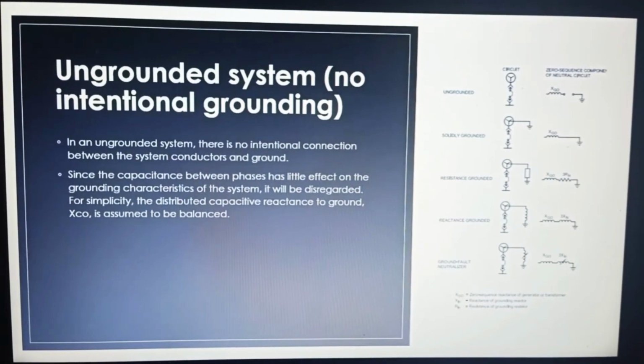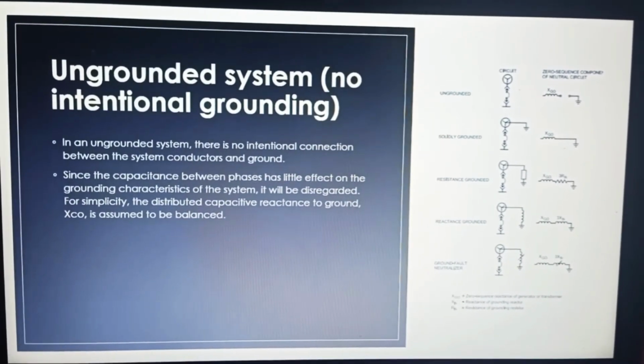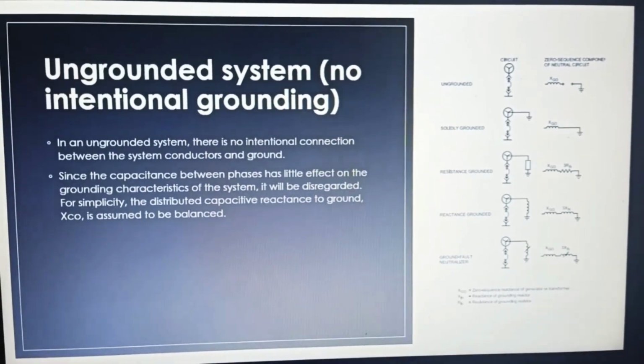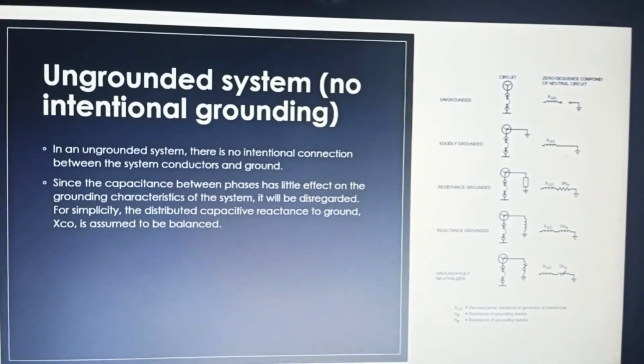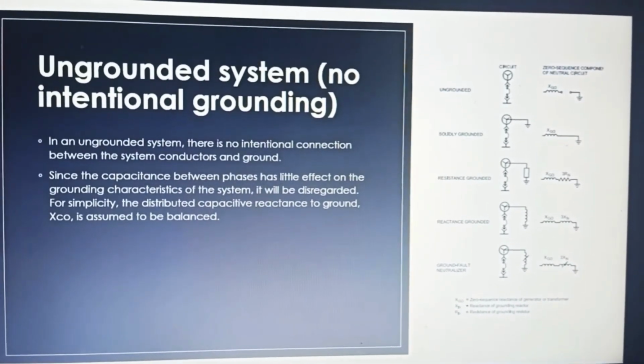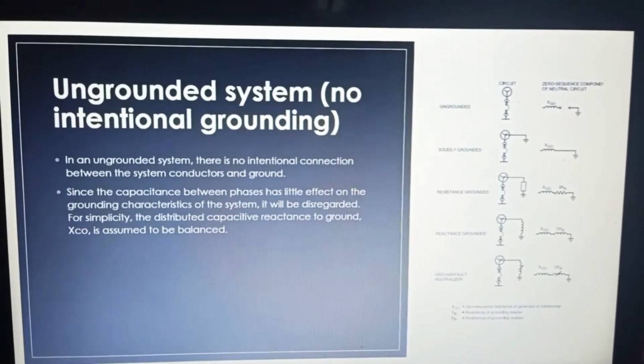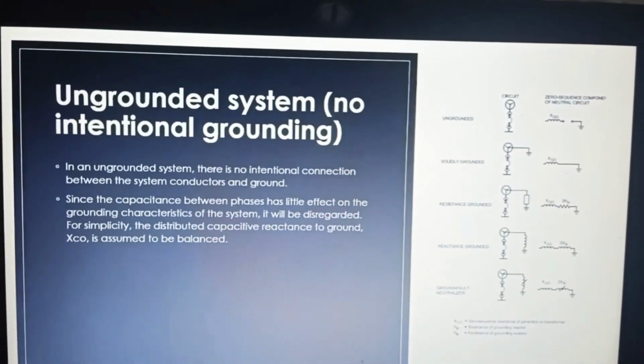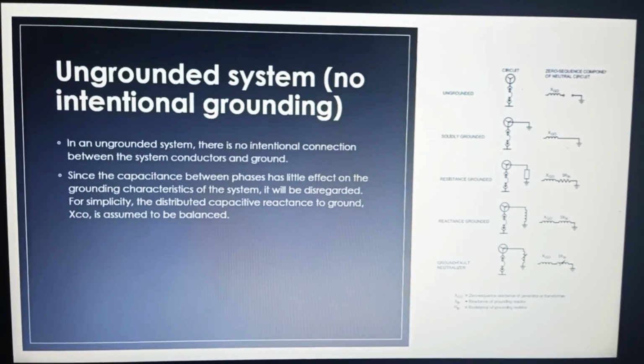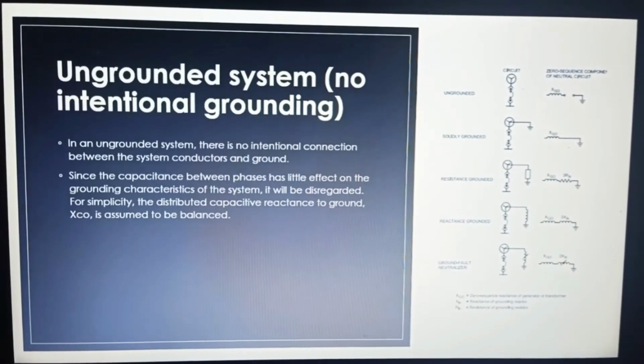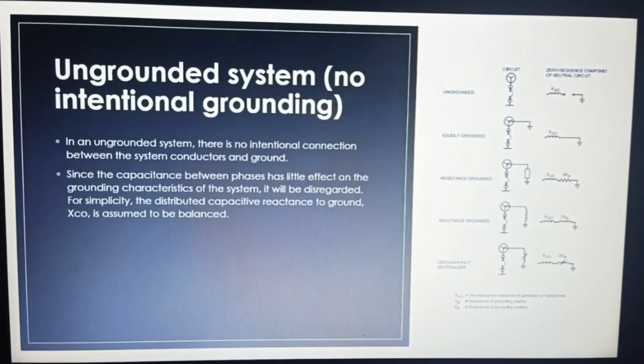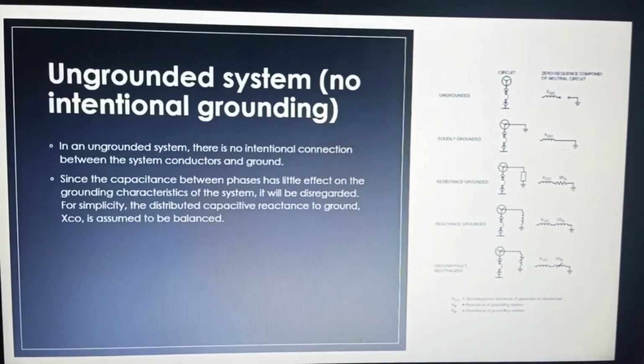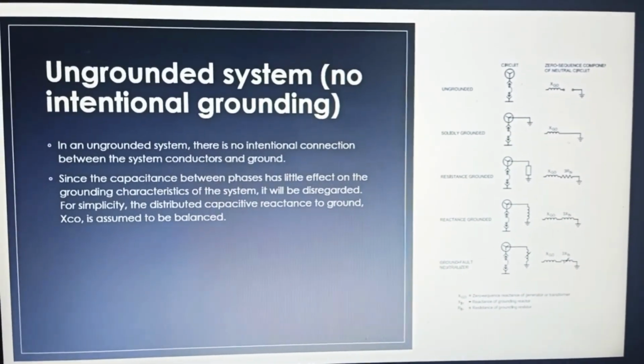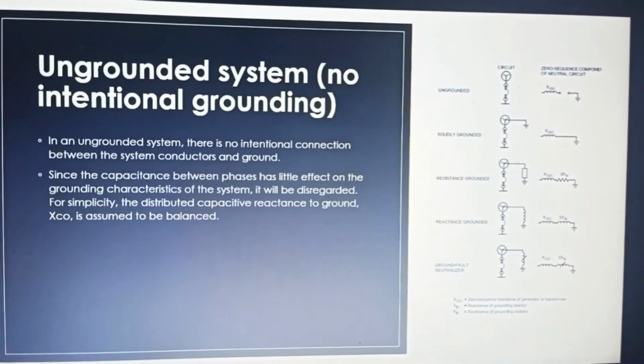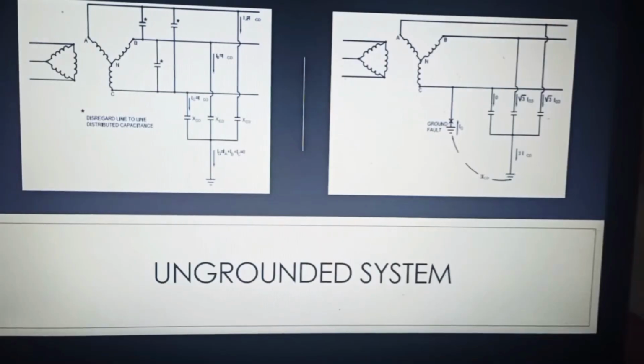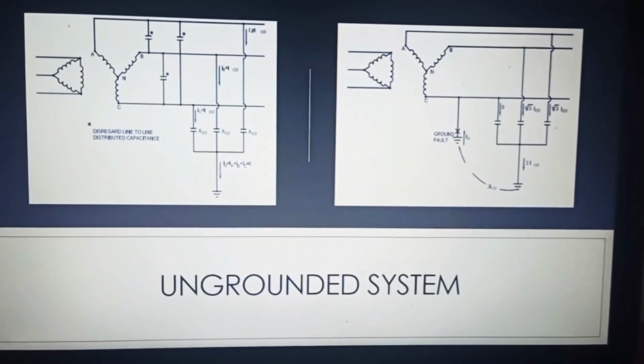In an ungrounded system, there is no intentional connection between the system conductor and ground. However, as shown in this figure, there always exists a capacitive coupling between one system conductor and another, and also between the system conductor and ground. Consequently, the so-called ungrounded system is in reality a capacitance grounded system, by virtue of the distributed capacitance from the system conductor to ground. Since the capacitance between phases has little effect on the grounding characteristic of the system, it will be disregarded. For simplicity, the distributed capacitive reactance to ground is assumed to be balanced.